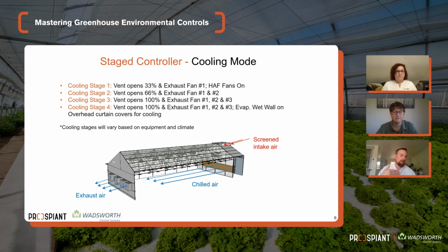Let's just say you're doing everything you possibly can. The pad wall is working to its maximum capacity to cool the greenhouse. You're using all your exhaust fans. You just can't get the greenhouse cool enough. Now the only option you have is to reduce the light levels, which is usually the last thing you want to do, depending on the crop. If you have a high light loving crop, the last thing you want to do is close the shade curtain if you're exceeding your temperature levels inside the house.